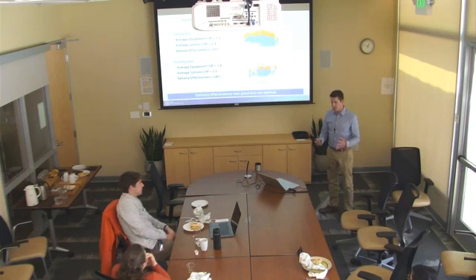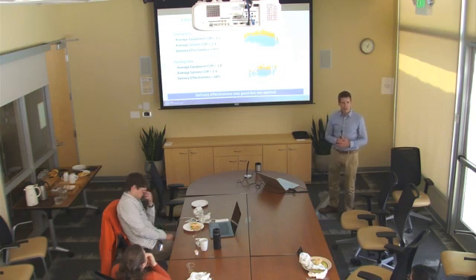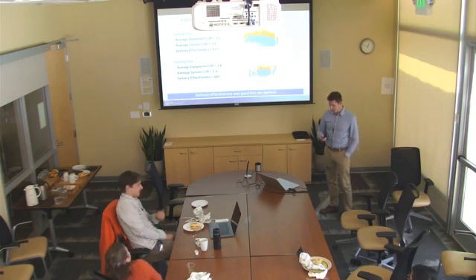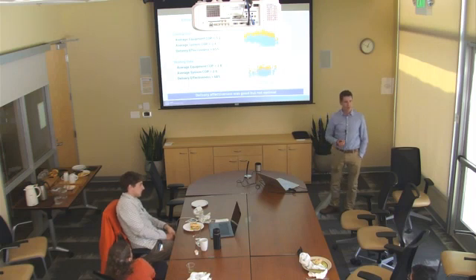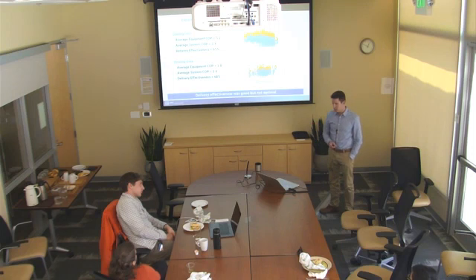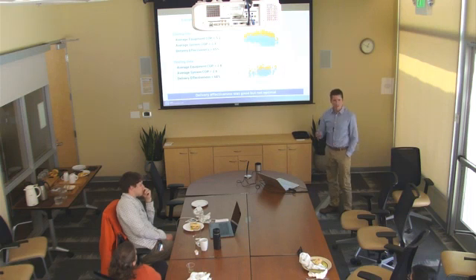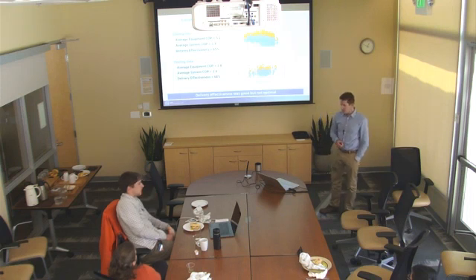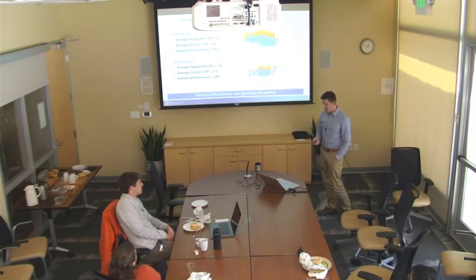It looks like the duct delivery effectiveness was about 65%. So it wasn't terrible. These houses all had zoning, and this particular house had R8 ducting. So it was kind of a good situation, but the zoning was definitely not optimized using the algorithms we could potentially develop through this research. It was just doing its normal zoning operation, which isn't looking at efficiency. It's more about comfort. And then on the heating side, you'll see again the equipment COP was fairly good at 3.8.